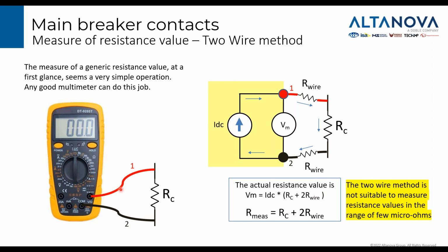In order to measure the resistance, you have to inject current and measure voltage. And the current source is inside the multimeter here. It is better represented in this scheme. So the current that is generated flows into the wires, and these wires go to the contact. So I cannot avoid measuring the contact resistance and also the resistance of the two wires. It's very unlikely that the resistance of the two wires is much less than a few microohms. So this is not a possible test that you can do.